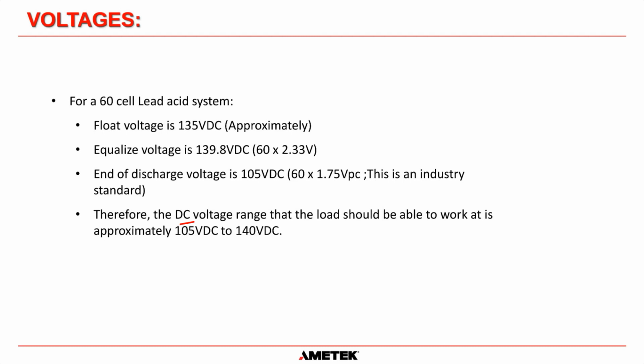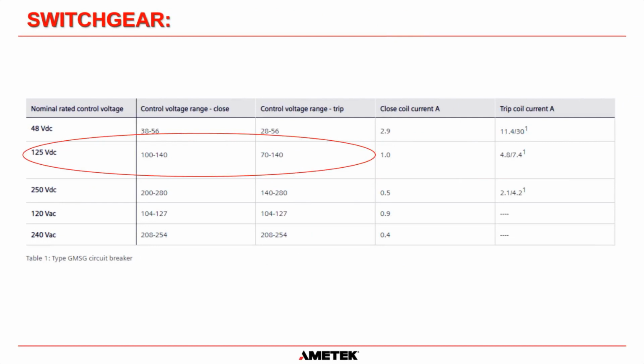When we have a battery installed in a system, that battery has to conform to the load circuits. In this next slide, this is actually from the specifications for a GMSG circuit breaker. I think that's an Eaton breaker. I can't remember, but it's a switchgear tripping and closing breaker. And it's saying the nominal, if it's a nominal 125 volt system, and on a side note, I hate it when they use 125 volts as the nominal. That's actually 120 volts. 120 and 125 volts are interchangeable. I don't know where 125 came from, but 120 is the actual nominal voltage because it's 60 cells usually.